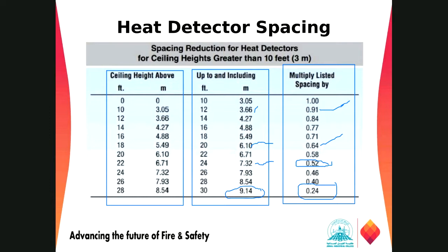So those listings by the manufacturer are based on a smooth ceiling at 3 meter height. At the field condition, you have to make sure regarding the height of the building and all, using this table from NFPA 72 and apply the rules.